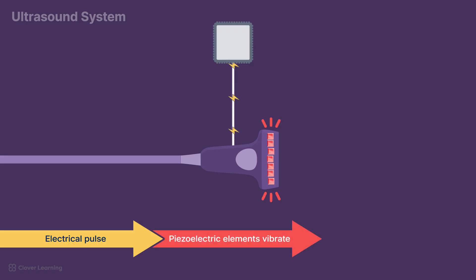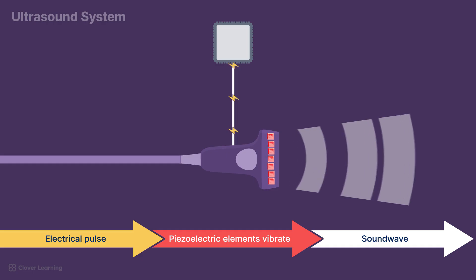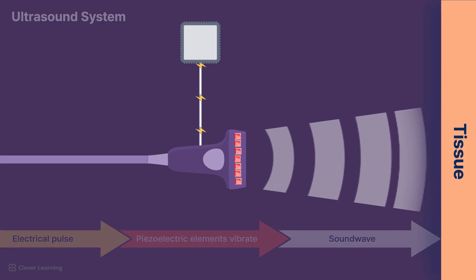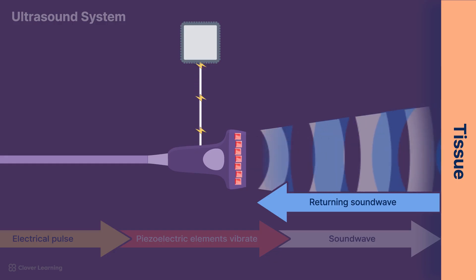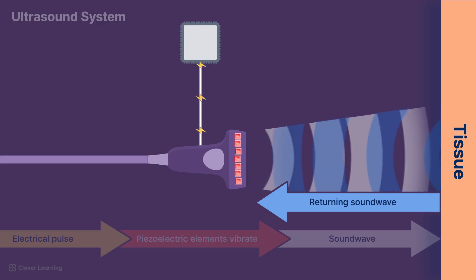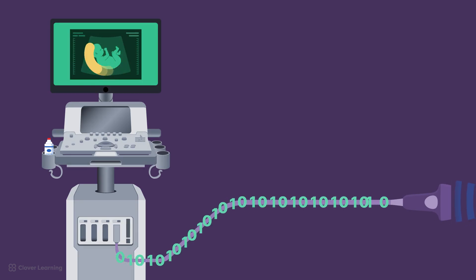To understand how the system forms an image, it helps to think through the full cycle. The pulser sends an electrical signal to the piezoelectric elements inside the transducer. The elements vibrate and produce sound waves, which travel through the body. As these waves encounter tissues, some of the sound is reflected back to the transducer. The transducer elements then convert the returning echoes into electrical signals, which are processed into digital data, converted into a visual format, and displayed as an image in real time.